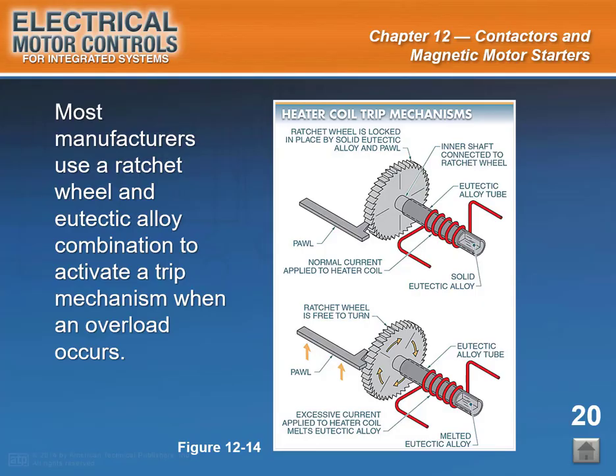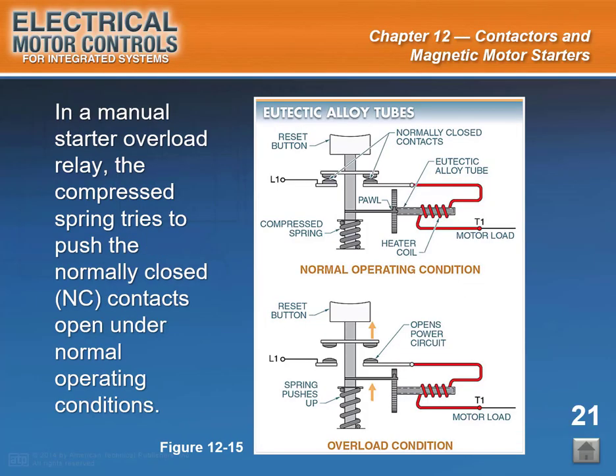Excessive current applied to the heater coil melts the eutectic alloy. This allows the ratchet wheel to turn freely on the eutectic alloy fluid. End of slide 20. Start of slide 21. Slide caption: in a manual starter overload relay, the compressed spring tries to push the normally closed contacts open under normal operating conditions. See Figure 12-15.